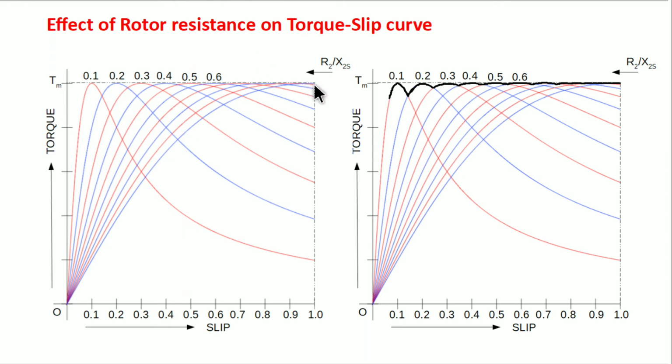What we do, as the motor picks up some speed, is change the resistance to a lower value, gradually going on decreasing, and the torque follows the next torque curve, and then the next curve, further decreasing. When at this resistance the torque is working on this curve, then reaching here we change the resistance so that it follows the next curve, next curve, next, and so on.